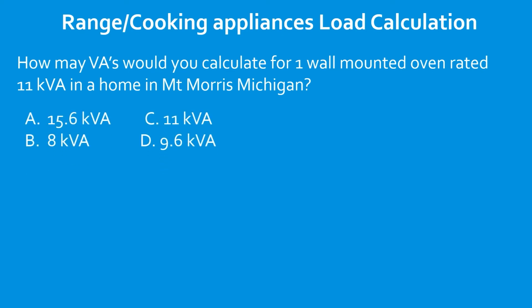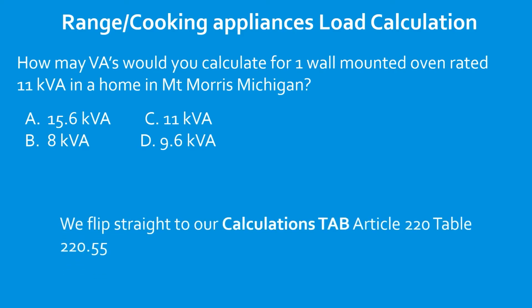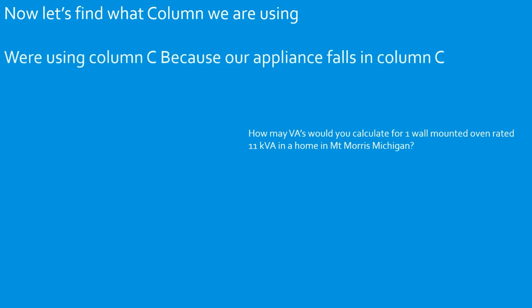Morris, Michigan? All right, so we're just dealing with one appliance. Now, if the question ever says branch circuit, then we're going to be using note 4. But since it doesn't mention anything about branch circuit, we're just going to go through the normal motions. So we flip straight to our calculations tab, Article 220, Table 220.55. All right, now let's figure out what column we're using. So we reread our question. We have one appliance. It is 11 kVA. So we're going to be using column C. So we start on our left-hand side for our number of appliances. We come over to column C for one range, and we're going to find out that the answer is 8 kVA. Let's get to it.